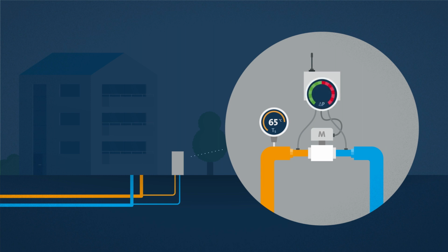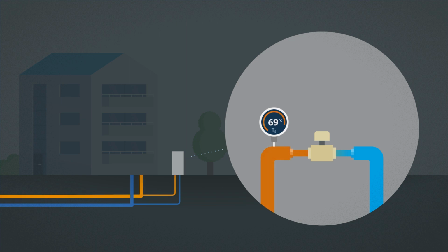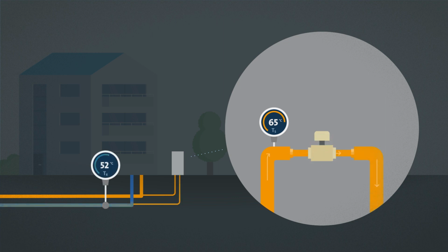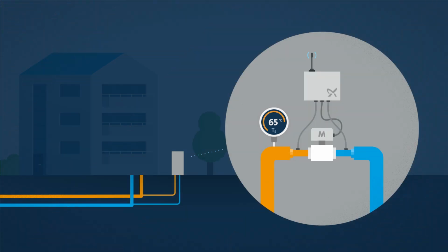Typically, district heating companies do not have data about differential pressures in the critical point, and instead, they operate with a safety margin. By utilizing data from the iGRID bypass, we can lower the differential pressure to meet the actual demand, thereby eliminating the need for overcompensation. Lowering the supply temperature without replacing the existing mechanical bypass results in excessive bypass flow and a higher return temperature. This can be monitored and avoided by remotely adjusting the set points in the motor valve of the iGRID bypass.